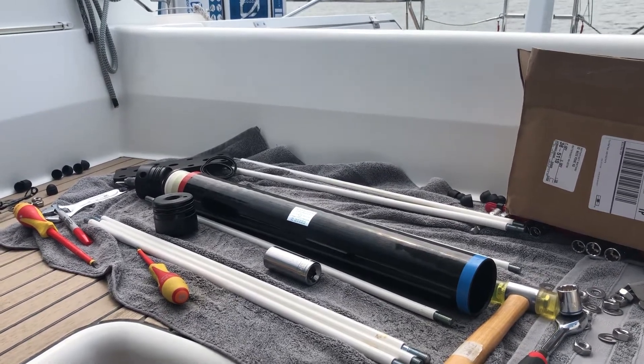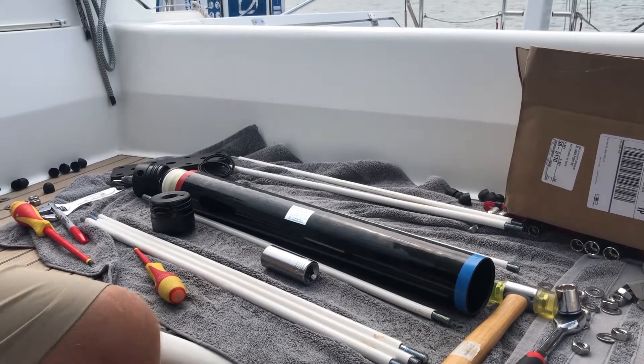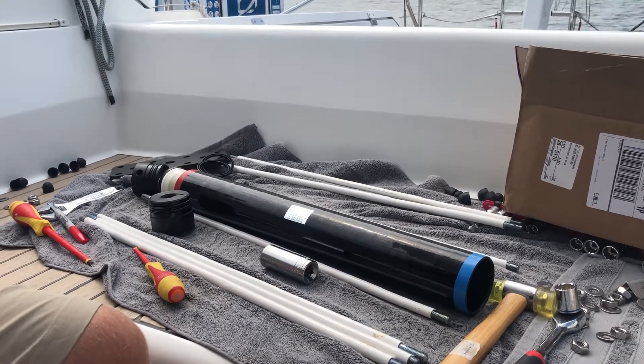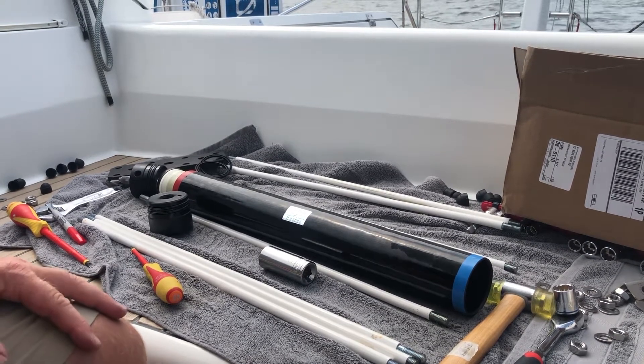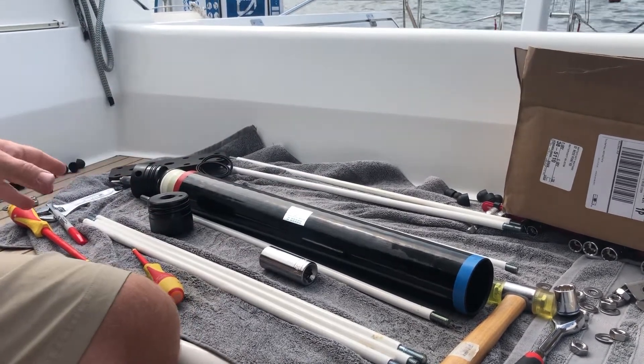I'm going to show you how to change a membrane, or at least cover some hints and points on changing the membrane on a desalinator or water maker. The boat is an Amel 50. There is a PDF on Dessalator's website that does explain how to do this, but not having ever done it before, I was having a little trouble, so I worked my way through it.